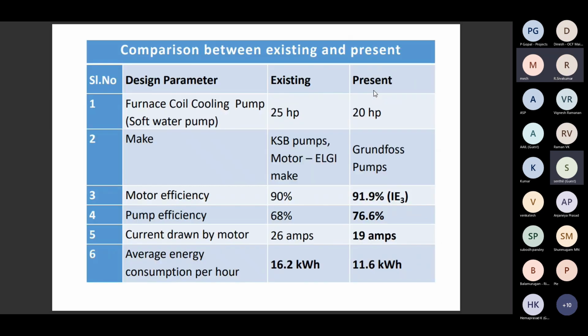So the existing is 25 HP, present is 20 HP, and the motor efficiency 90. The new pump motor efficiency is 91. Existing pump efficiency is rated at 68, but the actual we don't know. We cannot measure the flow rating and other things. If we are able to measure the flow rating and head, we can exactly say the existing pump efficiency, and the new pump efficiency rated is 76.